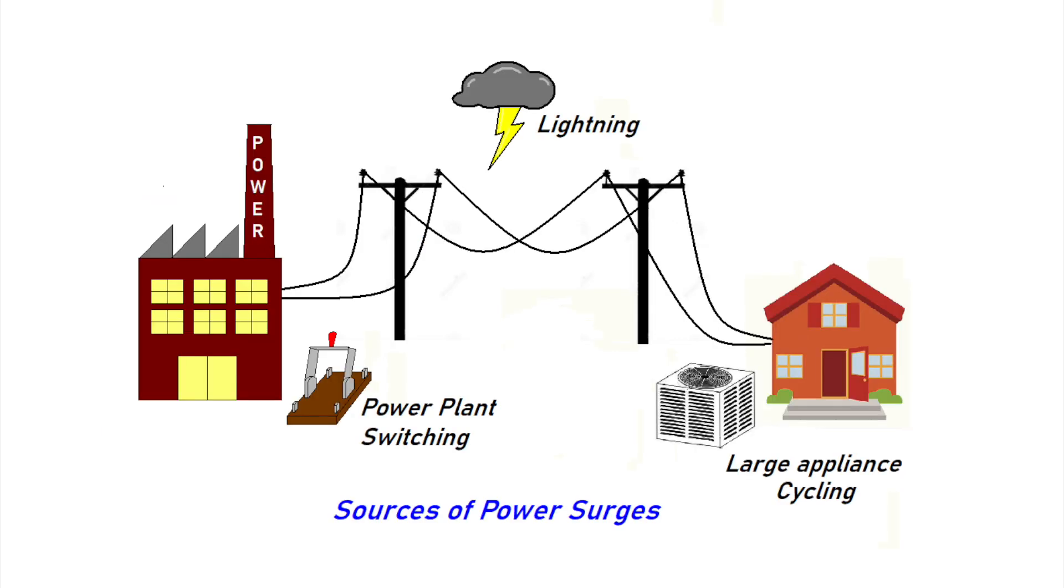So where do surges come from anyway? The NEMA estimates that 60-80% of surges are created within a facility. Surges are typically caused by switching transients, like motors starting and stopping, as well as compressors. And the remaining 20-40% are caused by external events, such as lightning and power grid switching at the power plant.